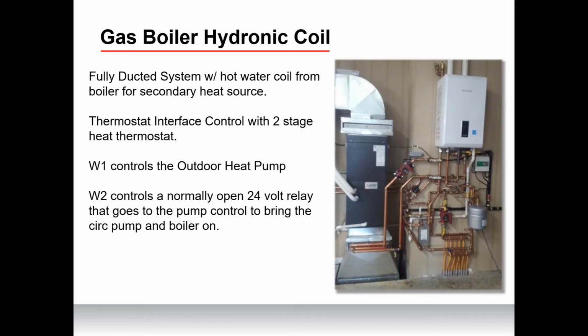The same control strategy utilizing the thermostat interface can be used for a gas boiler hydronic coil and fully ducted air handler system like we looked at earlier. Here, the thermostat interface will be paired with a third-party two-stage heat thermostat. W1 of the thermostat will control first stage heat at the outdoor heat pump, while W2 would control a normally open 24-volt relay that goes to the boiler pump control to bring the circulator pump and boiler on as second stage heat. This is very simple. It's a cost-effective way of integrating a dual fuel heating strategy. Once again, it's very, very simple.